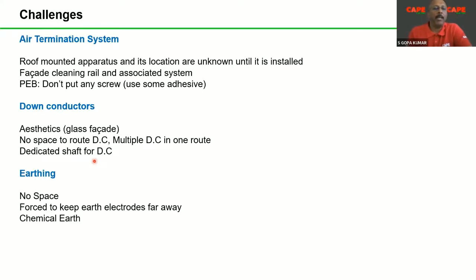If a typical building requires 10 down conductors, all the 10 must run outside the building, preferably all around the building, as straight as possible. So routing the down conductor through the dedicated shaft is also practically not possible. It is a violation of the standard. Then when it comes to earthing, most of the buildings don't have any space. There is no space, no soil, because probably we have to buy some land from the neighbor to put an earth electrode.